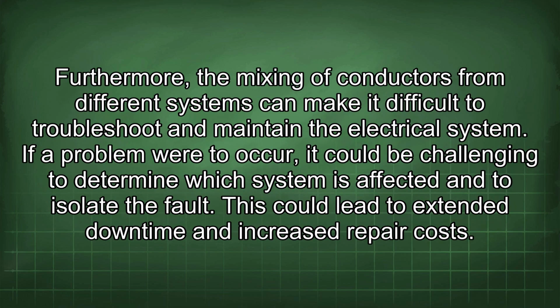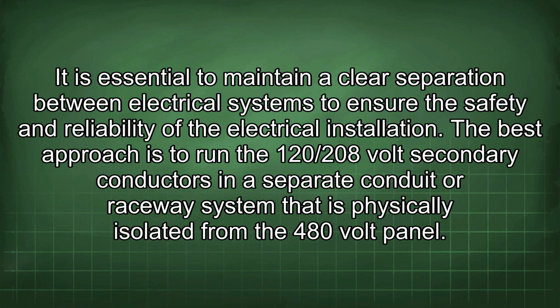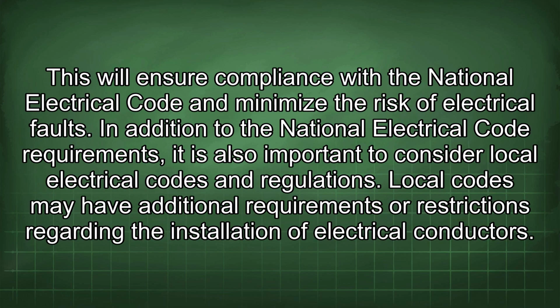Furthermore, the mixing of conductors from different systems can make it difficult to troubleshoot and maintain the electrical system. If a problem were to occur, it could be challenging to determine which system is affected and to isolate the fault. This could lead to extended downtime and increased repair costs. It is essential to maintain a clear separation between electrical systems to ensure the safety and reliability of the electrical installation. The best approach is to run the 120/208 volt secondary conductors in a separate conduit or raceway system that is physically isolated from the 480 volt panel. This will ensure compliance with the National Electrical Code and minimize the risk of electrical faults.